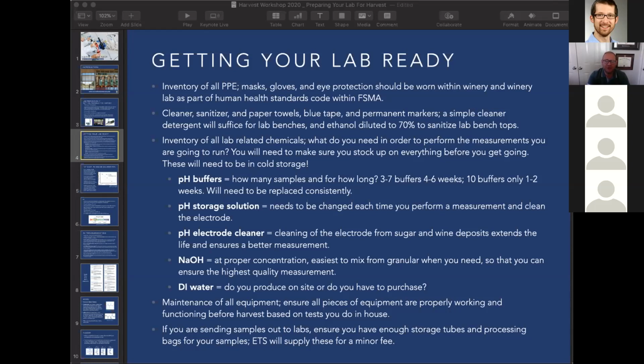I would say make sure you stock up on everything. And I just put a little list here because let's say we're just doing pH, TA and Brix. The biggest thing that we want to have enough of is pH buffers and storage solution. You never want your electrode to dry out. You never want it to be exposed to oxygen for a long period of time. And you also want to make sure that your pH buffers are fresh, and that your NaOH is fresh if you're doing any sort of titration with that strong base.